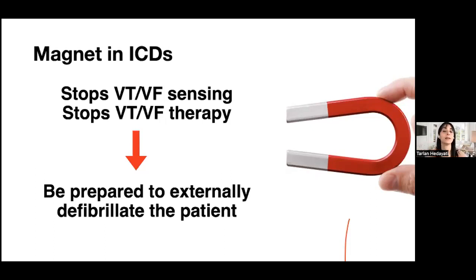In an ICD, if you turn the sensing function off, the device is not going to recognize VTAC or VFib. The problem is that it will not defibrillate VTAC or VFib. So in effect, by turning the sensing function of an ICD off, you are also turning off the therapy of the device. This is the critical thing you have to remember before you put a magnet on a device: does the patient have a pacemaker or do they have an ICD?